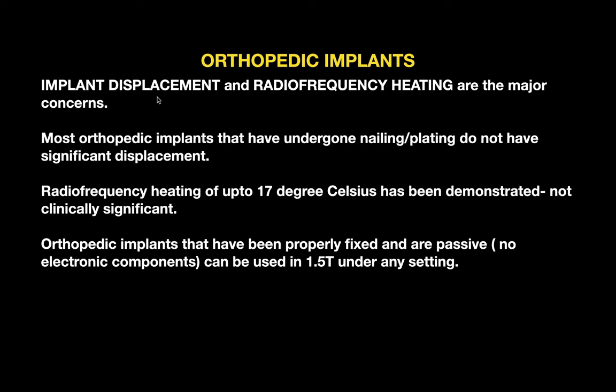Regarding orthopedic implants, the two major concerns are displacement of the implant and radiofrequency heating. Most orthopedic implants that have undergone nailing and plating do not have significant displacement. Heating up to 17 degree Celsius has been demonstrated in implants but has no clinical significance. Orthopedic implants that are properly fixed and passive can be used at 1.5 tesla under any setting.